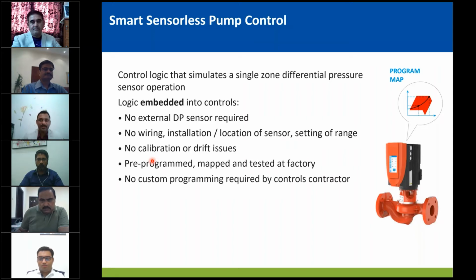Calibration is a challenge. Once you install and commission, often sensors are not calibrated. That's been a challenge for many operation and maintenance teams in the buildings. So they are prone to drift over time, whether it be scaling, air loss, or some other sort of damage. Pre-programmed, mapped and tested factory configuration can bring benefits and avoid all of these risks and challenges associated with the sensor and its installation. You don't need to do any custom programming from the BMS or controls contractor end. Once you have an integrated embedded control on a smart pump, it will take away the risk of all the above items.